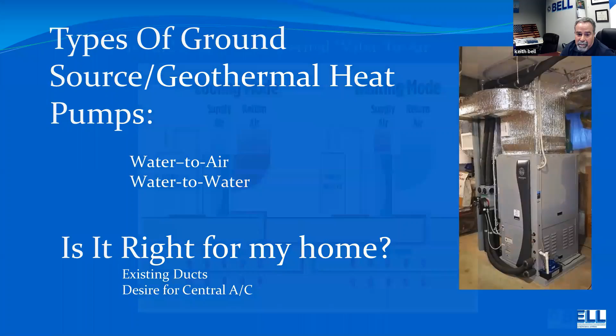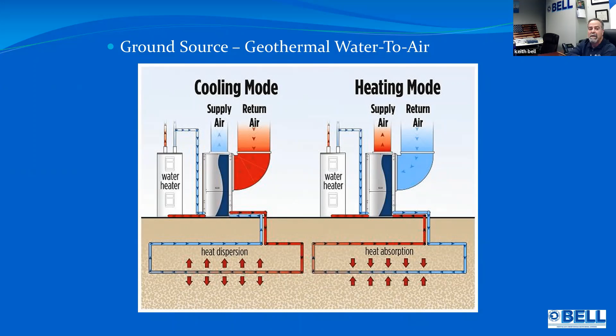Ductwork, yeah. So here's a little schematic of how it works. This is water to air. It provides hot air, cold air, and there's a thing called the desuperheater operation. When the units are running in the summertime, they're basically giving you free hot water, because you're rejecting that heat into the ground anyway. And in the wintertime, it takes about 3 to 5% off your capacity, but it helps you make your hot water all year long.